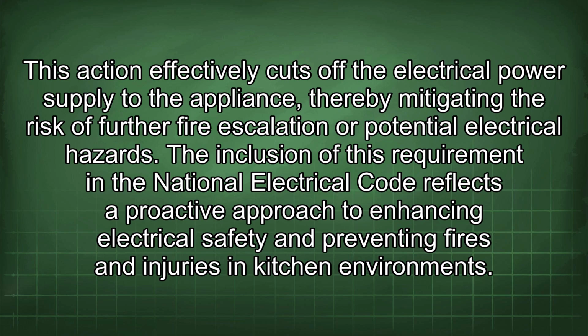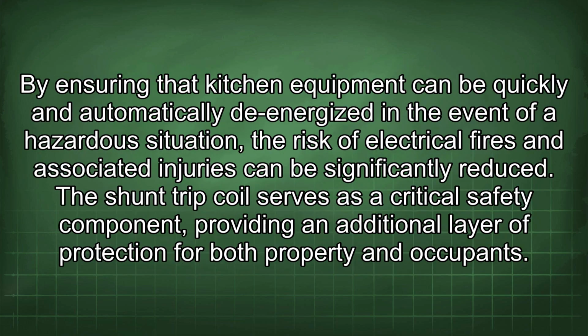or potential electrical hazards. The inclusion of this requirement in the National Electrical Code reflects a proactive approach to enhancing electrical safety and preventing fires and injuries in kitchen environments. By ensuring that kitchen equipment can be quickly and automatically de-energized in the event of a hazardous situation, the risk of electrical fires and associated injuries can be significantly reduced.